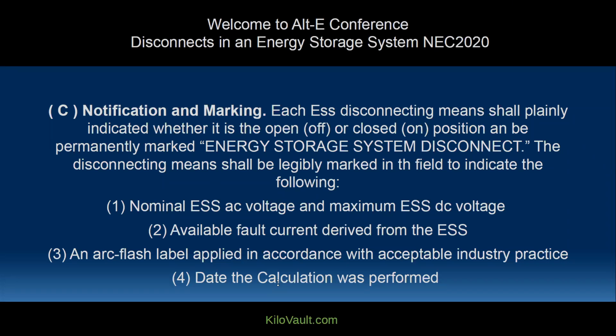Okay. Well, let me see if I can just try interpreting this as it's written out here. It comes a little tricky. If your whole energy storage system, say the inverter, charge controllers, the actual batteries, are on a building external from the residence. This includes your PV array. You only have, say, like an AC line going to the residential panel in the home. Don't see you're going to be needing to disconnect that point because it's not going to be within the home at that point for the 1 or 2 family homes. It's where the code's a little vague on, even though the system is supplying that home at that point.